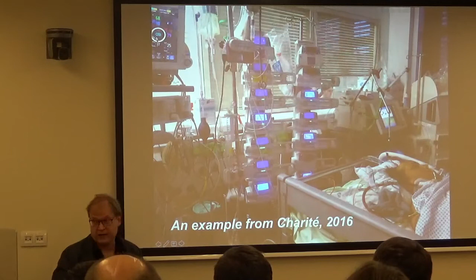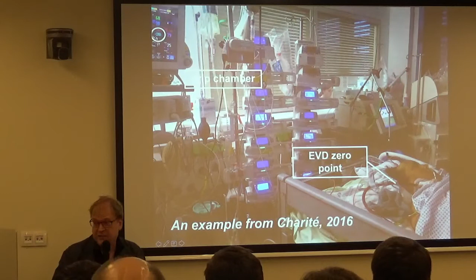The drip chamber was mounted here. So there's no way this EVD could work, because there was a little bit of difference between them. If you look at the zeroing point, it's difficult to recognize from just a 2D picture. The transducer is about here, and I took my ruler and measured. The transducer was below the zeroing point.